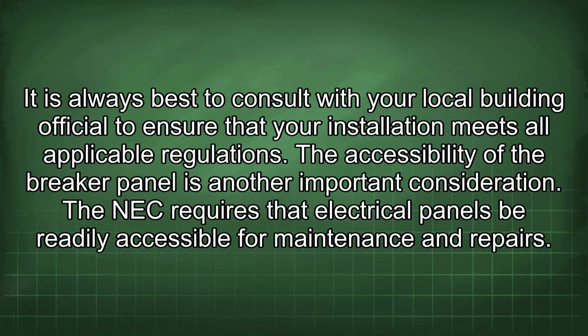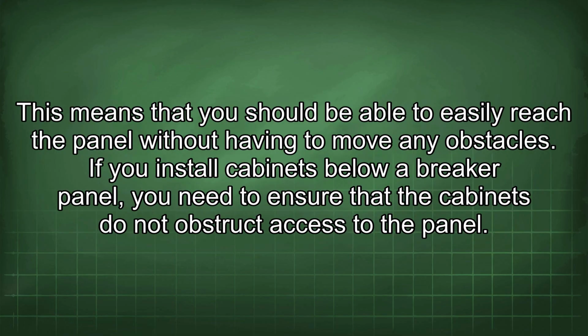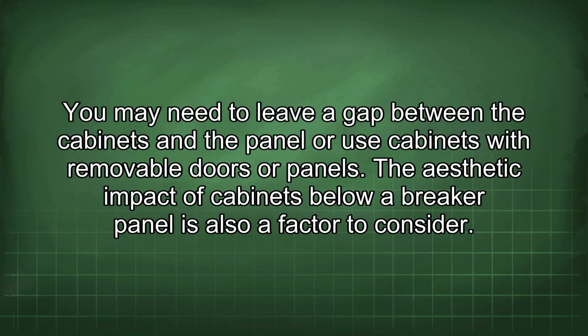The accessibility of the breaker panel is another important consideration. The NEC requires that electrical panels be readily accessible for maintenance and repairs. This means that you should be able to easily reach the panel without having to move any obstacles. If you install cabinets below a breaker panel, you need to ensure that the cabinets do not obstruct access to the panel.